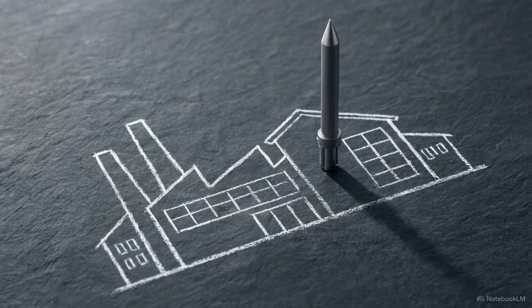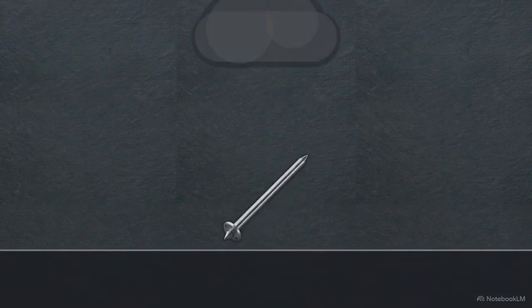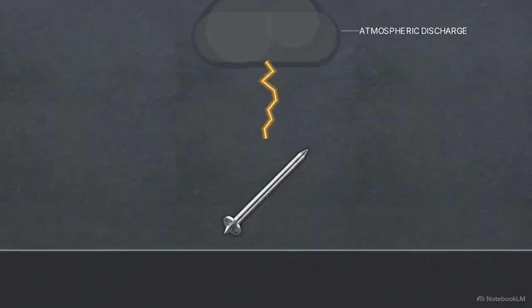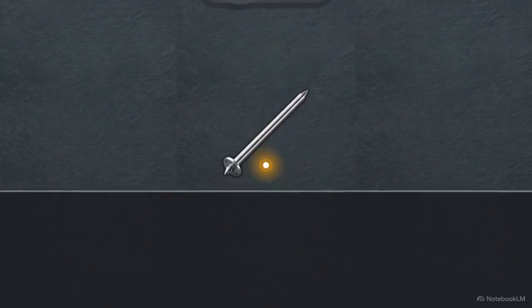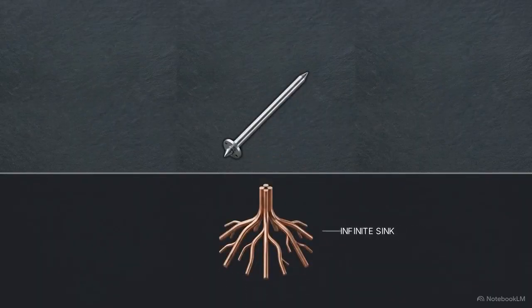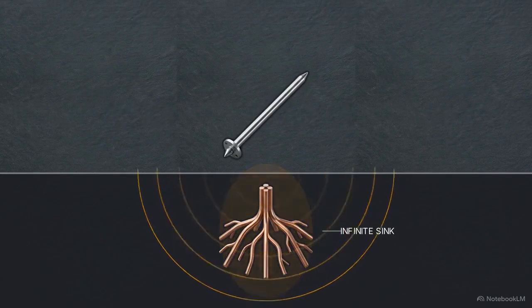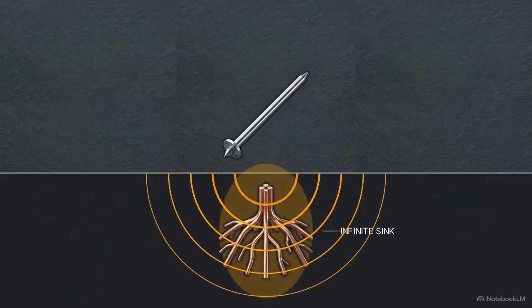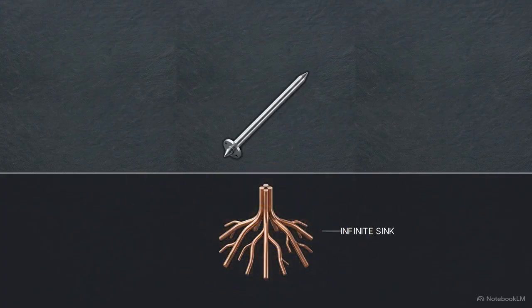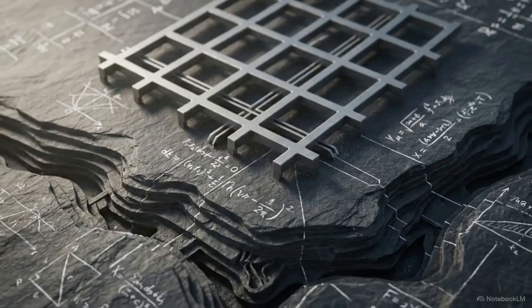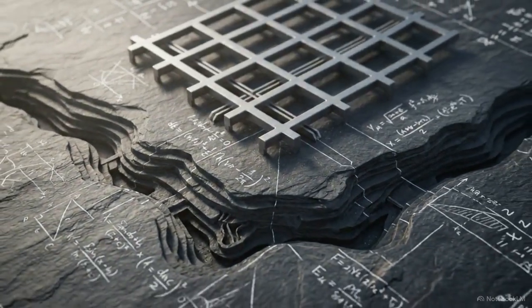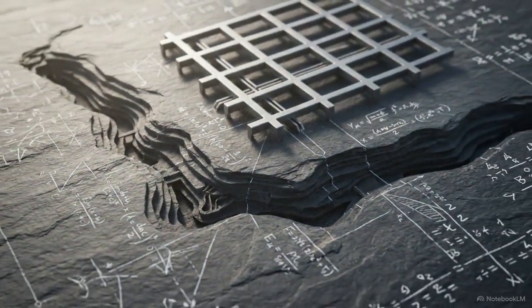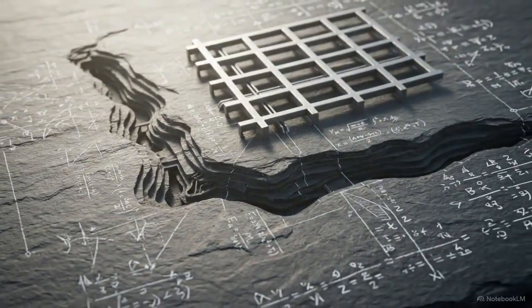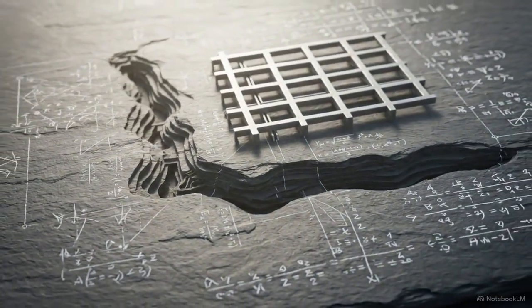Beyond internal system faults, we must also engineer protections against macroscopic external events. A lightning bolt represents a massive, instantaneous injection of atmospheric electrical energy into a localized area. To manage this influx, the earthing system forms the essential backbone of all lightning arrestor networks, catching and routing the cloud discharge arc. Whether mitigating microscopic static friction or routing a massive atmospheric discharge, the physical Earth serves as the infinite sink required to prevent equipment destruction.